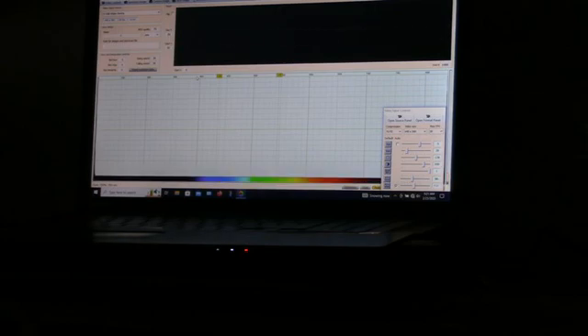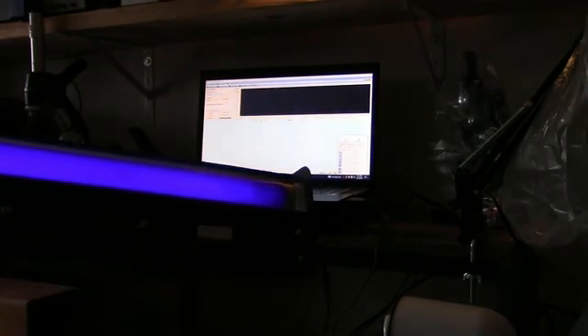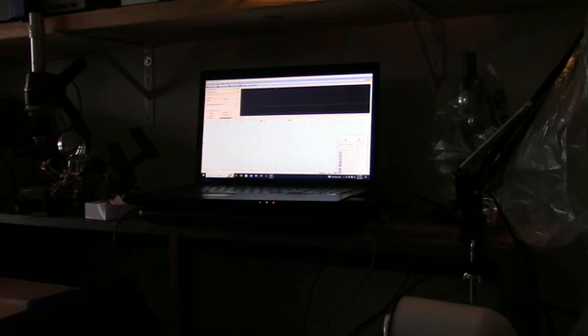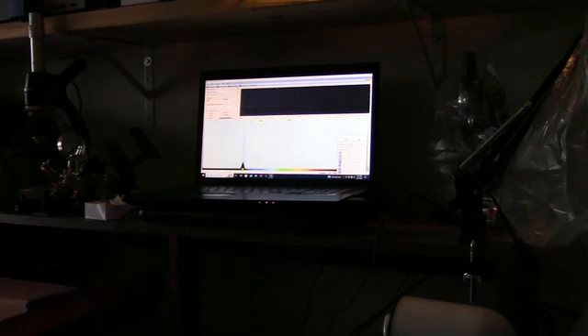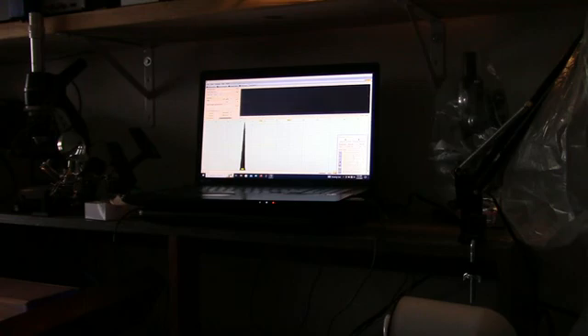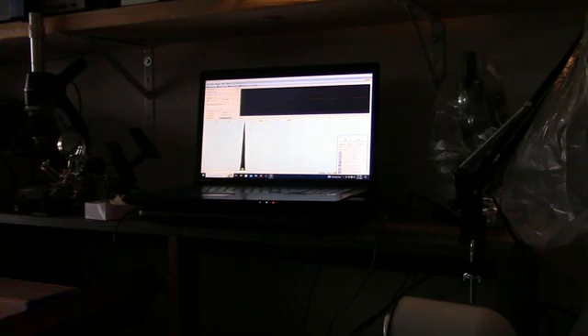Next I'm going to use a black light fluorescent black light and see if we can look at the spectrum of that. So here's the light, the black light, holding it in front of the slit. Here you can see the spectral line here of this black light, and it looks to be on this scale about 380 nanometers. Now this is fairly relative. This isn't real accurate but it gives you an idea.